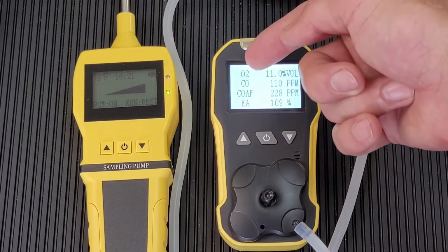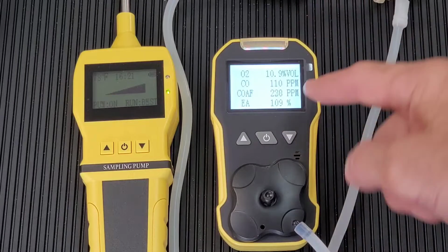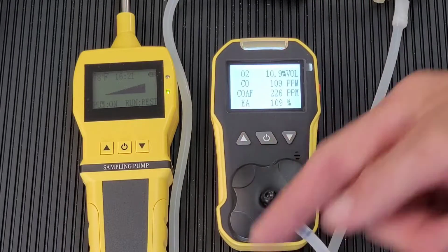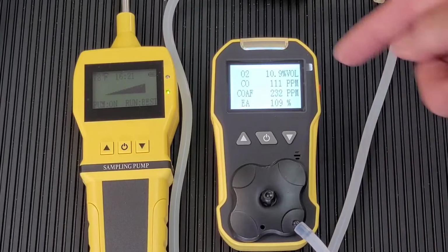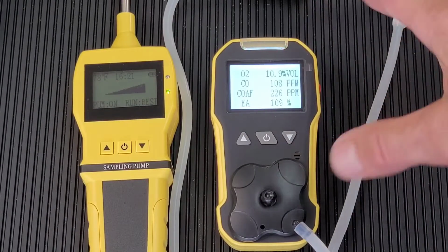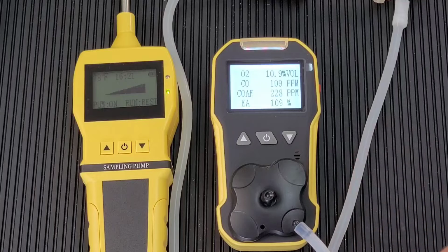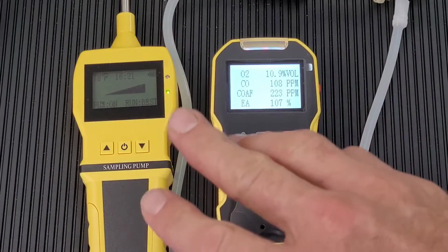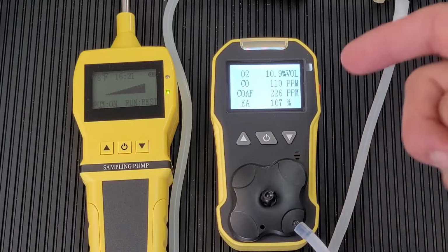So as the digits change from the sensor, you see the COAF and excess air being recalculated. Okay, folks, as you can see, going 10.9, 10. It's been about a minute since I put the gas on, but it takes a good minute for it to stabilize, and that's what we recommend in the instructions of this basic combustion analyzer setup, folks. So there you go, not bad.